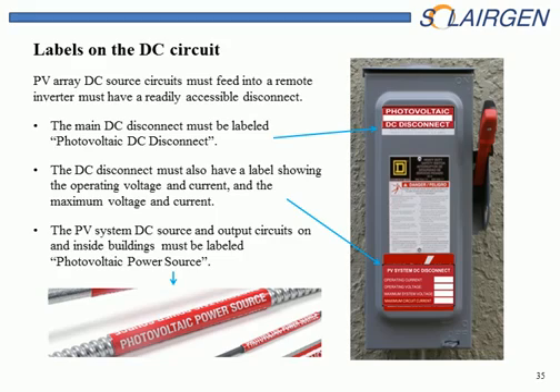The NEC requires that the DC disconnect be labeled as shown in this picture, and also labeling the operating voltage and max voltage and current. And it also requires that we have some type of a labeling on the source conductors. So if we have conduits running to the inverter from the PV array, they have to be identified some way like this, very brightly, with the photovoltaic power source. This has only been in the last few years of enforcement, so anything installed prior to that probably does not have this label on it. They all have the DC disconnect, but readily accessible, as we said before, can be on the interior of the structure. So this may not be where you can actually get to it readily.